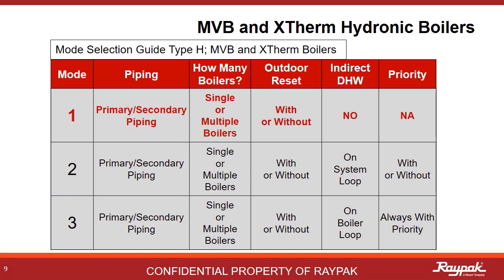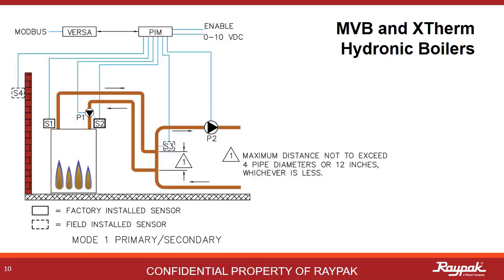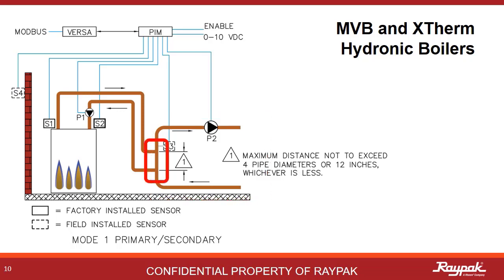We will discuss the details of Mode 1 first, as it is by far the most common. Here is a diagram for a Mode 1 primary-secondary system with a single boiler. It's primary-secondary because there are two loops: the boiler loop and the system loop. That's how you should refer to them — the boiler loop and the system loop — not the primary loop and the secondary loop. The place where the two loops overlap is called the decoupler. The decoupler is the magic of a primary-secondary system. When built properly, this will allow the bigger system pump to run when the boiler is not running without forcing water through the boiler.